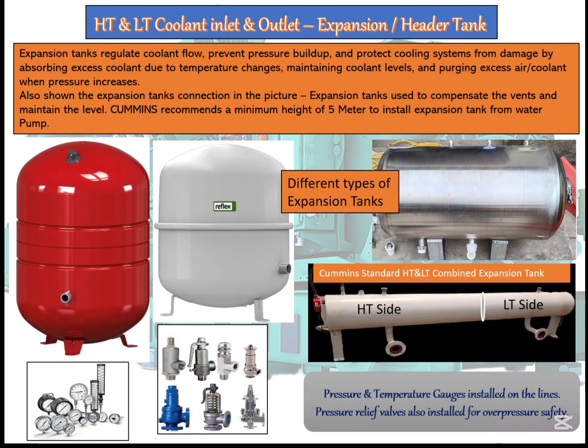On the lines, for safety, we can also use temperature and pressure gauges and overpressure switches that provide for system safety. If we are using this bladder type, the red and gray one, we don't need to put it at the highest point. We can just install it with the engine on the floor. The bladder inside is rubber that can expand and squeeze with temperature changes and provide adequate cooling. But if we are using these other two types, we need to install them at a minimum height of 5 meters, where gravity gives us at least 0.5 bar pressure, then the make-up tank and all those things. So that's another difference between these types.